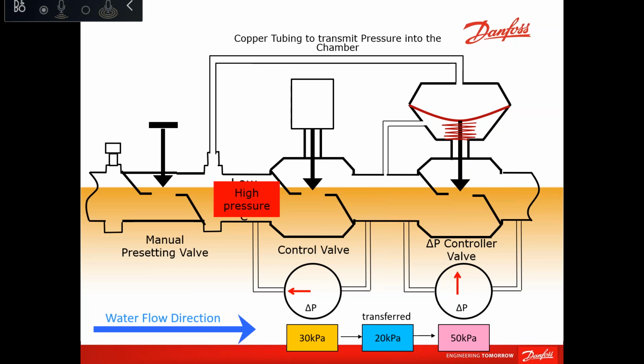So yeah, if 20% is your design flow, then yes, you can set it at 20%. But if I have a flow of 0.01 liter per second, and I'm sure that this flow is the design flow, then I would go to the equipment flow, which will be around 0.03, and try to increase the setting a bit, because then the actuator will modulate and control back to the 10% or 20% required.